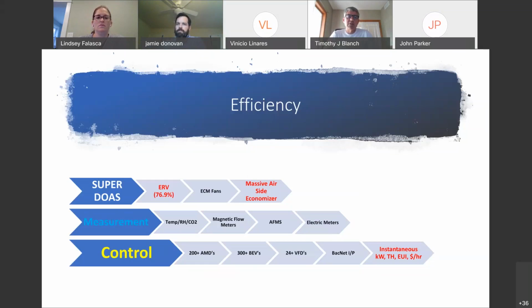And then we have a lot of electric meters. And finally, on the control level, I didn't describe that correctly. The airflow measuring damper is in the control level. We have airflow measuring stations, which are just measurement probes in the central plant. The DOAS units, but we have the damper devices throughout the building, about 20 per floor, all of the primary air and 4 exhaust AMDs per floor.